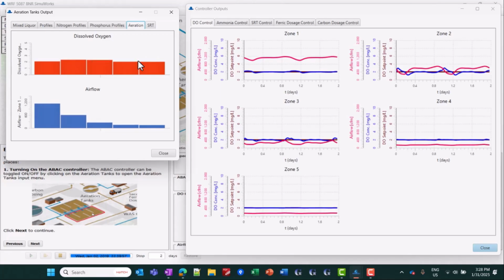What it's responding to is actually a change in a daily diurnal pattern of the influent loading. So the diurnal flow is going up and down during the day. And we can see, if I look at this time series here, this is time on this axis, 2 full days. We can see here that, for example, the brown line is the DO set point and the blue line is the actual DO. So it's not a perfect controller.